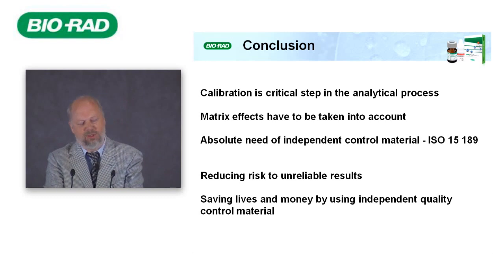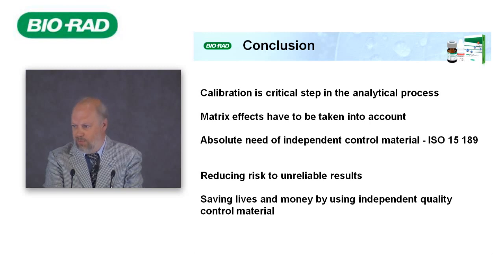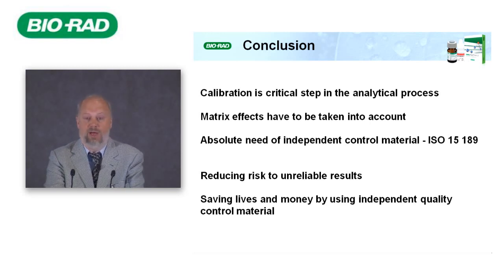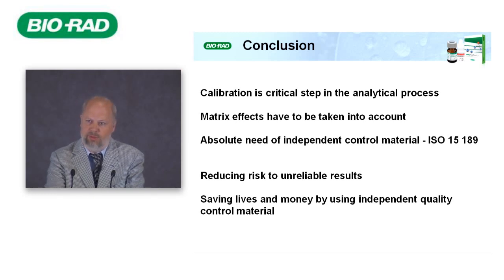My conclusions: calibration is a critical step in the analytical process. Matrix effects have to be taken into account. There is an absolute need for independent control material — third-party control — as required by ISO 15189, and it reduces the risk of unreliable results. Finally, you save lives and money by using independent quality control material. That's why on the plane they do checks again and again — and that's why we need this for the laboratory as well.